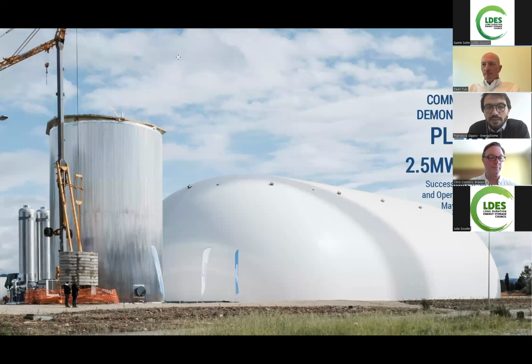We like to start our presentations from here because this is a very important milestone of our business development. This represents the first commercial scale plant operational: a 2.5 megawatt, 4 megawatt hour plant we built in Sardinia. It has been connected to the Italian national grid and operational since May 2022. This represents the last step of de-risking our technology before commercialization. In fact, 2.5 megawatts is the minimum size for us to have the right type of compressor and turbine, exactly the same type we're planning to use in the full-scale commercial plants now in the phase of commercialization.